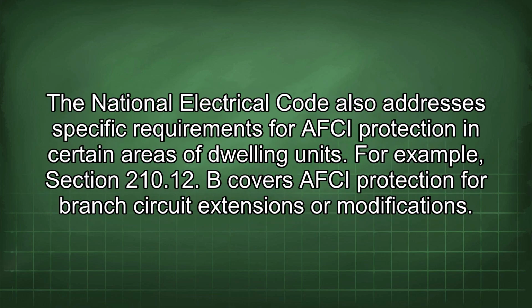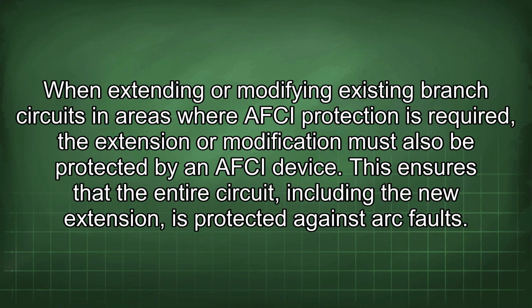The National Electrical Code also addresses specific requirements for AFCI protection in certain areas of dwelling units. For example, Section 210.12 B covers AFCI protection for branch circuit extensions or modifications. When extending or modifying existing branch circuits in areas where AFCI protection is required, the extension or modification must also be protected by an AFCI device. This ensures that the entire circuit, including the new extension, is protected against arc faults.